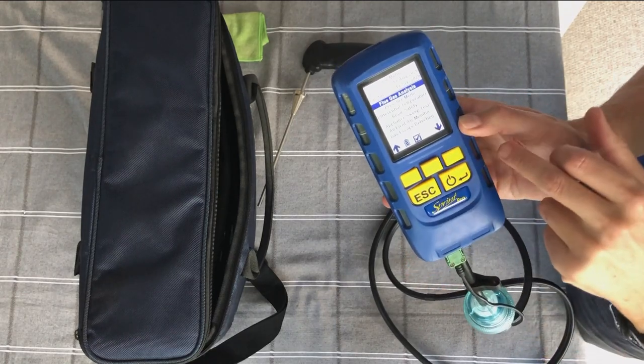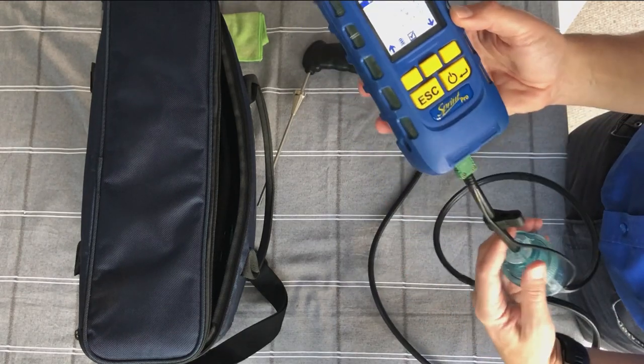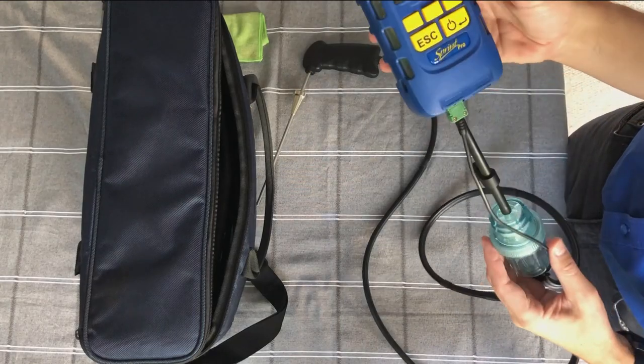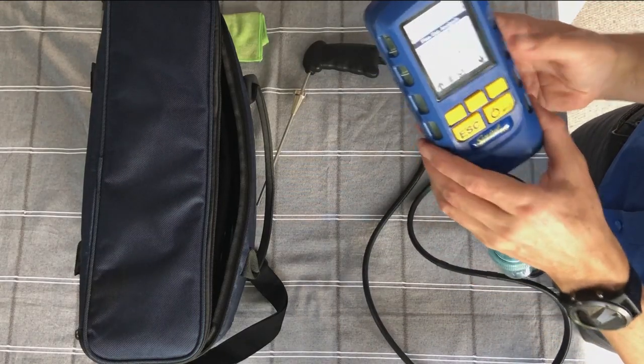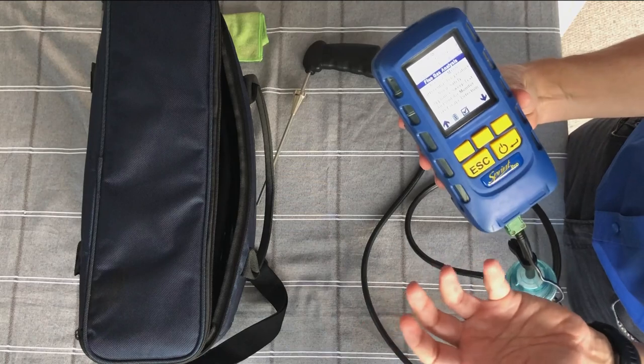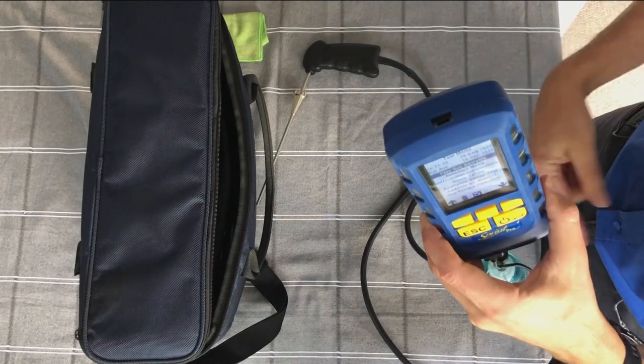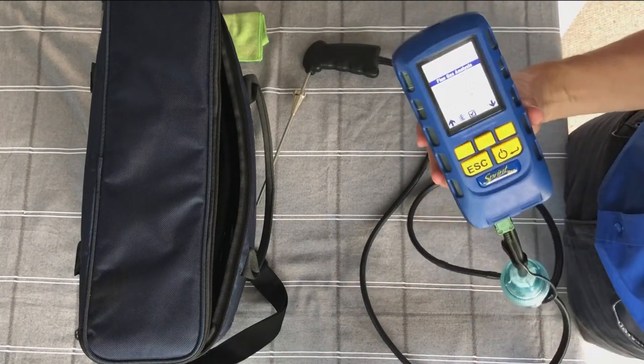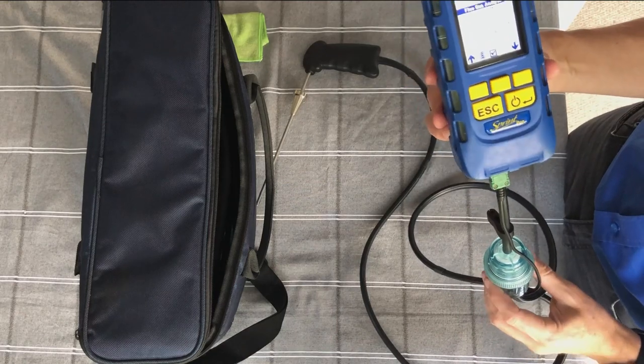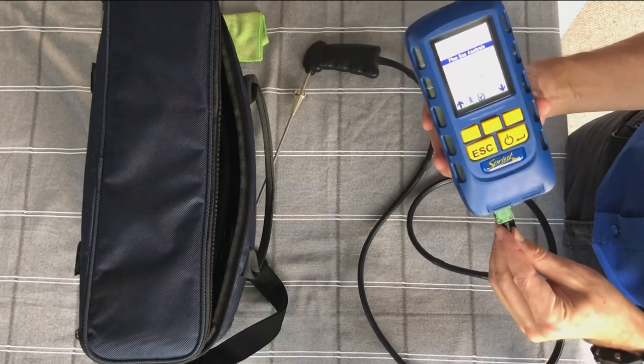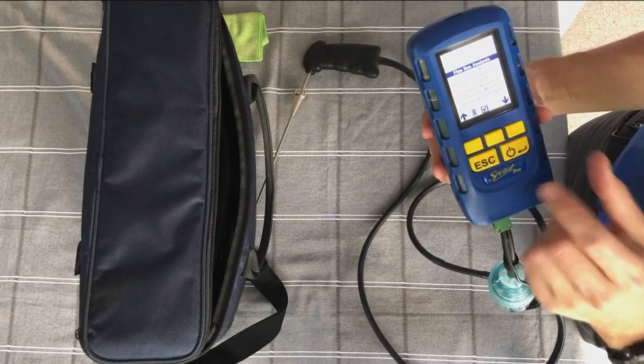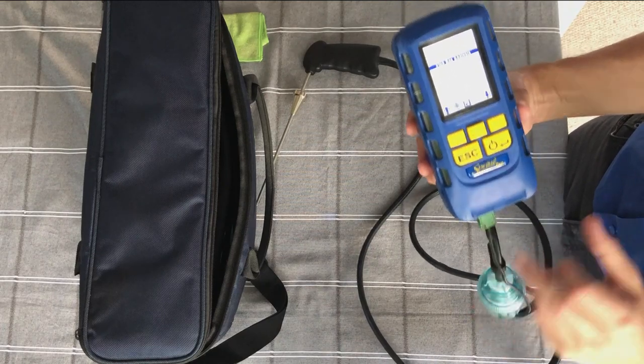I'm gonna go through this in order, but we'll start with flue gas analysis. As I've already done, I've connected up my instrument so that when I go into flue gas analysis and it does its initial purge or start up and zero, I'm actually purging the whole system. So any old residue flue gas that might still be in the system, I'm purging out before we do the zero. So that's quite important. So yeah, always turn it on with your probe connected.